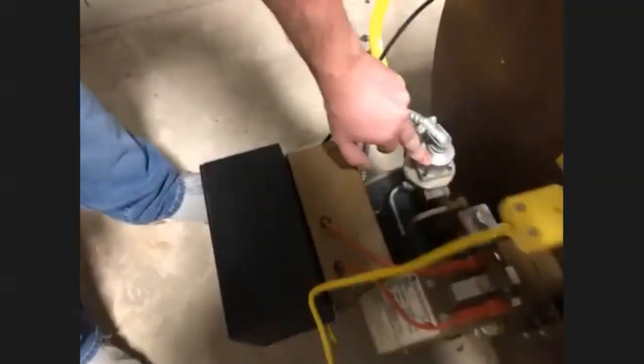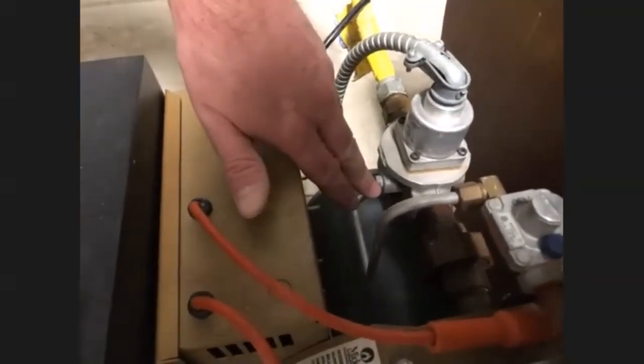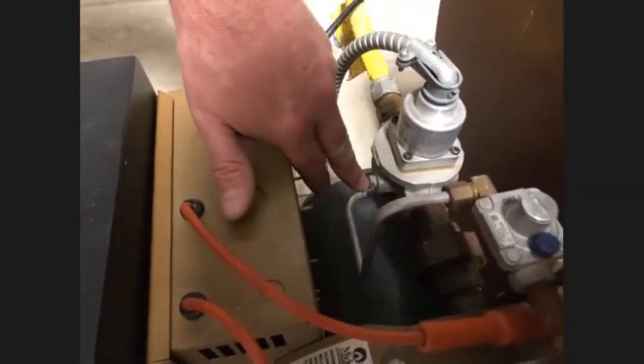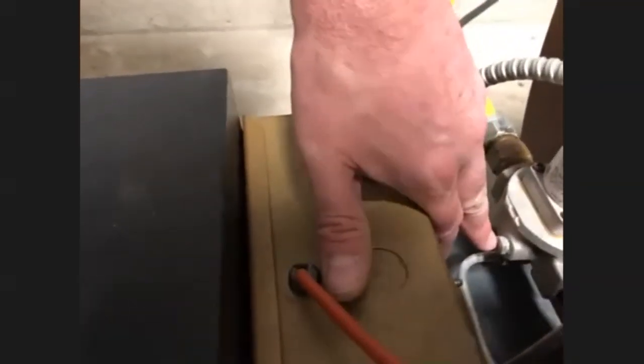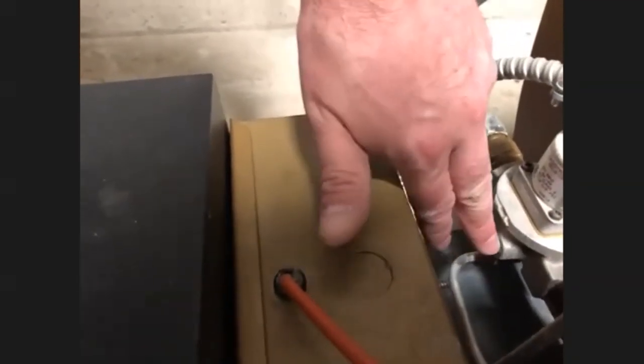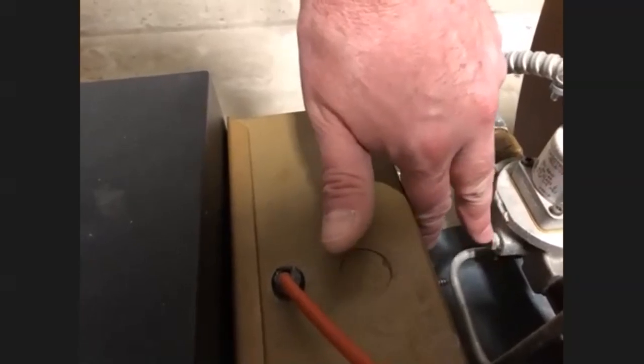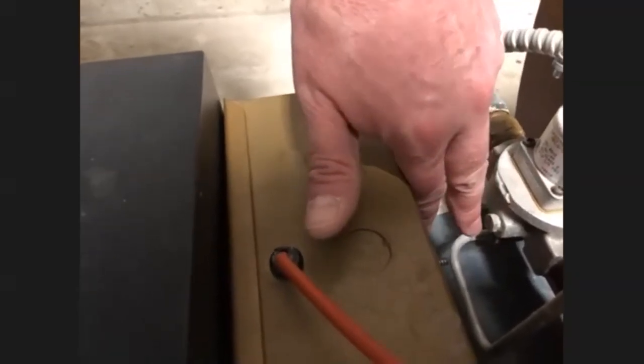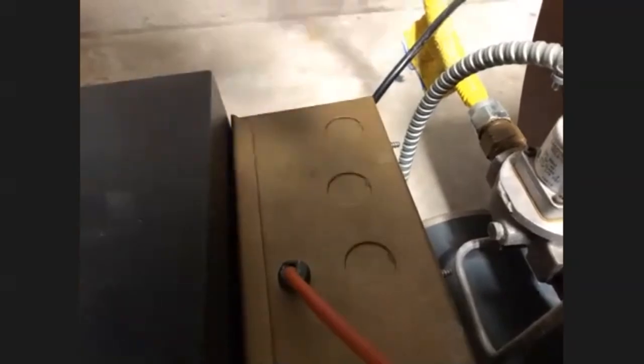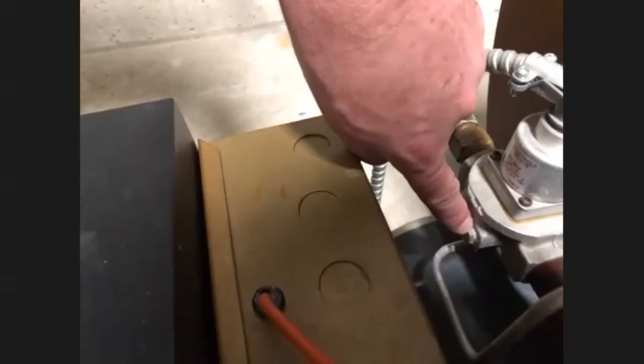When you are coming out of this regulator, there is also a secondary or pilot regulator as well. And there is a pressure tap on the main regulator right on the side. You want to put your manometer on there and make sure that you have 4 inches coming out of this pressure tap. You must do all this while you're operating. As you start it, try to do the ignition and verify that gas pressure as it's trying to run. Again, 4 inches of water column coming out of here.